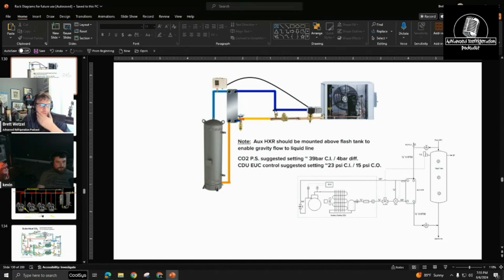That's why typically these units are mounted right above, because the heat exchanger needs to be above the flash tank for the thermal siphon effect. The vapor rises up, gets condensed, drops down, becomes liquid, and the cycle repeats to bring pressure and temperature down.